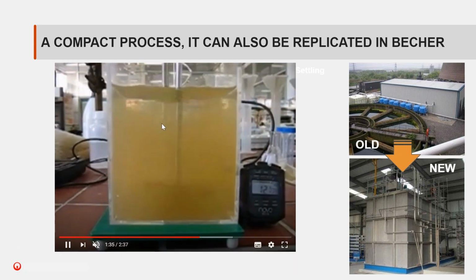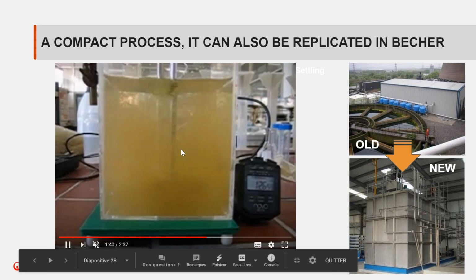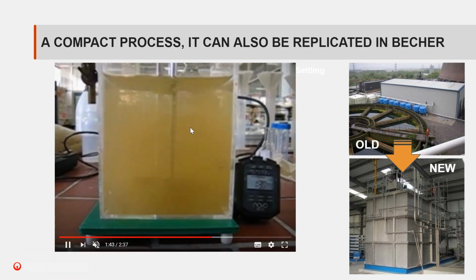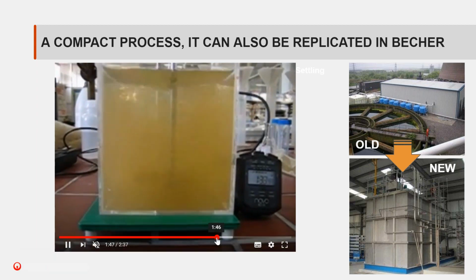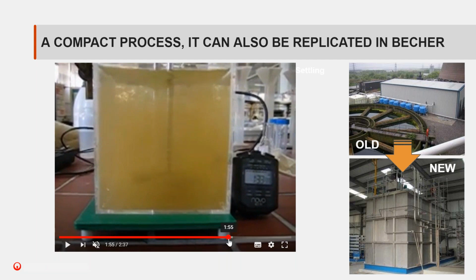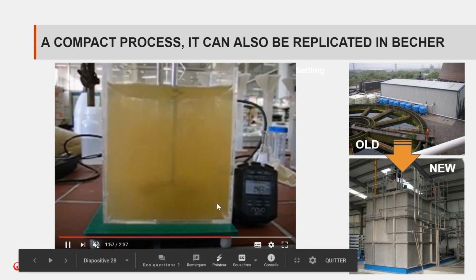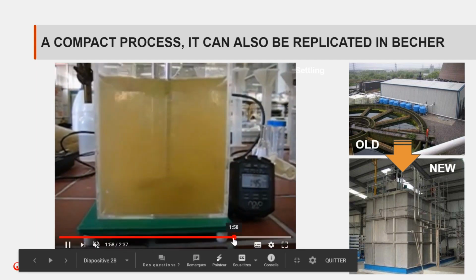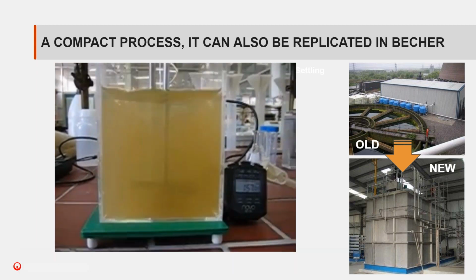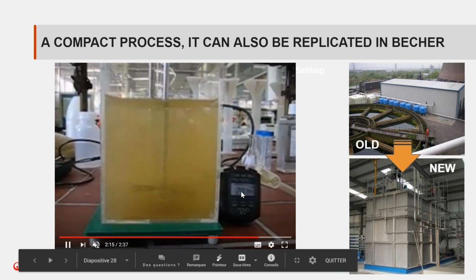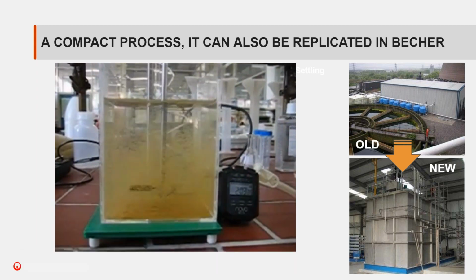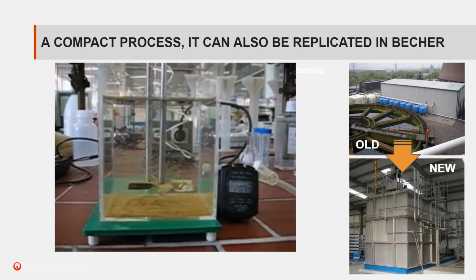We've adjusted the speed of the mixer to slightly slow it down, whilst still making sure the microsand is well in suspension. I'm going to speed up to 2 minutes, where we're going to start to stop the mixer. So we're there at close to 2 minutes. The mixer is now stopped. Within 10 seconds, all the floc is drawn back to the bottom of the unit.